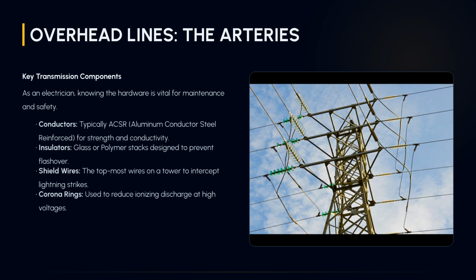Overhead lines are the grid's arteries. Key components include ACSR conductors for strength and conductivity, glass or polymer insulators to prevent flashover, shield wires to intercept lightning, and corona rings to reduce ionizing discharge at high voltages.